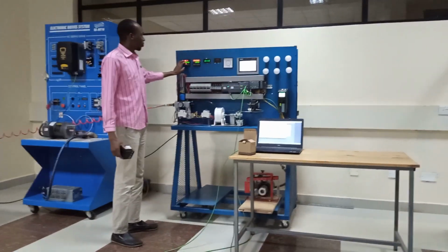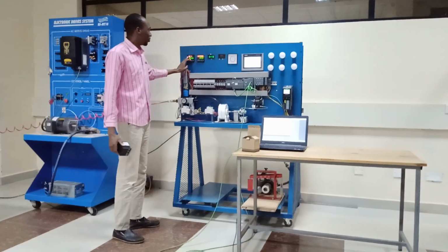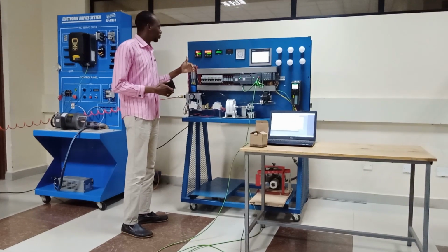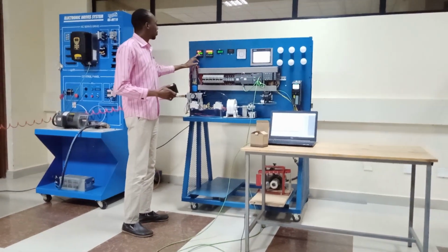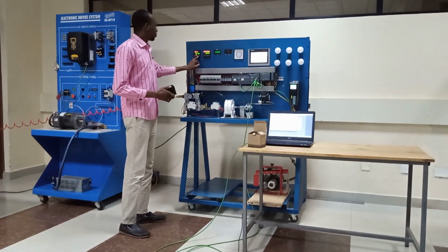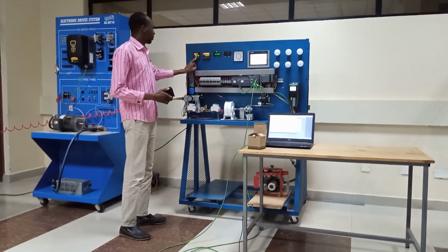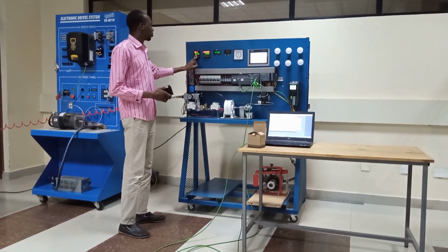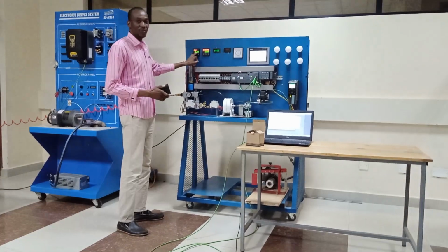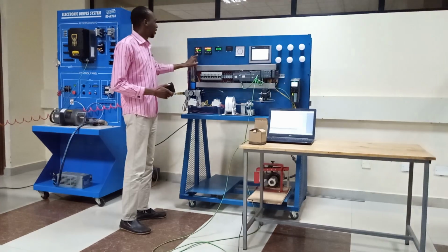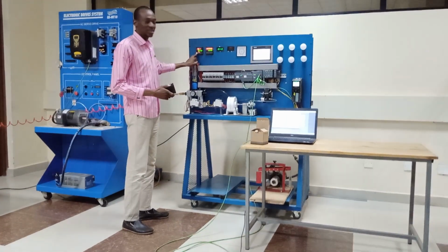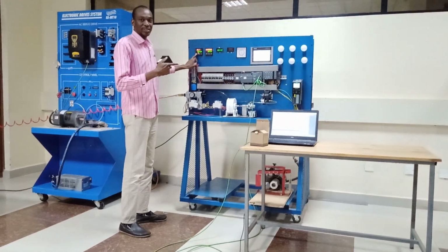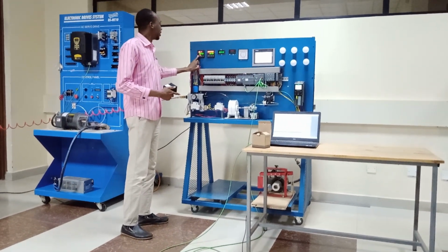First of all, we have the alarm. You have to set the alarm. We have an alarm low value and an alarm high value. To set the alarm high value, we have to lift from here, reset, then we lift till we get the value that we want. Here I have 45 Hz. Then to set, I have to press set. If I press set once, it's already set. Then I can move to the next.